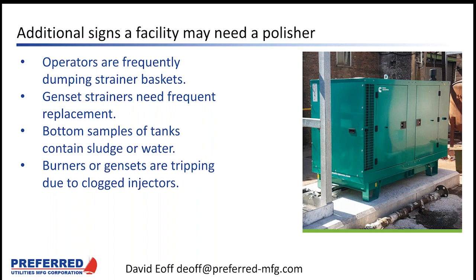But biosludge looks really different, and if you're getting biosludge in your strainers, that's an indication that you've got water in your tanks. If you bottom sample your tanks from time to time, like you should, look to see if they've got water or sludge in them. This is something that Preferred technicians do whenever they do a preventive maintenance on a fuel system: take a bottom sample of the tank and look at what's in it. If your burners or gensets are tripping due to clogged injectors, you likely have a water issue in your tank.